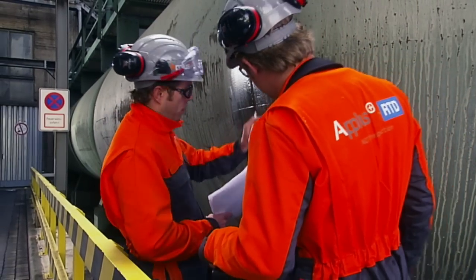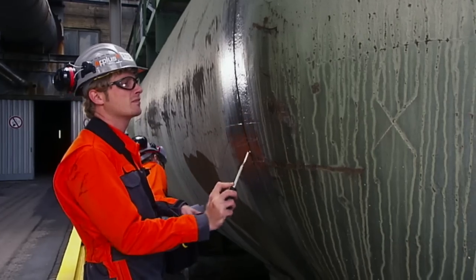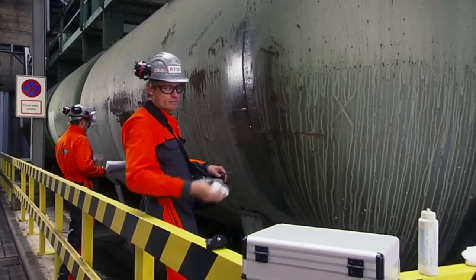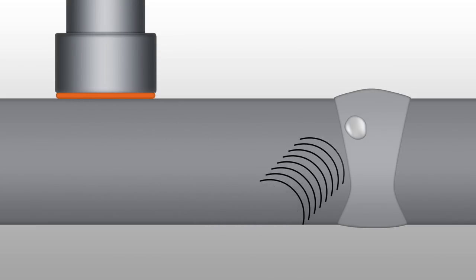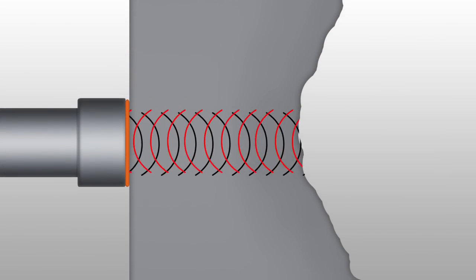It is possible to investigate whether there are discontinuities under the surface using ultrasonic sound waves. Ultrasound has such a high frequency that people cannot hear it. The vibrations can, however, be measured with sensitive measuring equipment. Using this storage vessel, a weld is checked for internal discontinuities. Sound waves are transmitted into the material with a transducer, and an echo is sent back from the rear wall or discontinuity. By registering this echo, we can deduce the thickness of the material, or if a discontinuity is present. In case of a discontinuity, sound is echoed back faster, allowing us to see if the material wall is thinning, for instance by corrosion.